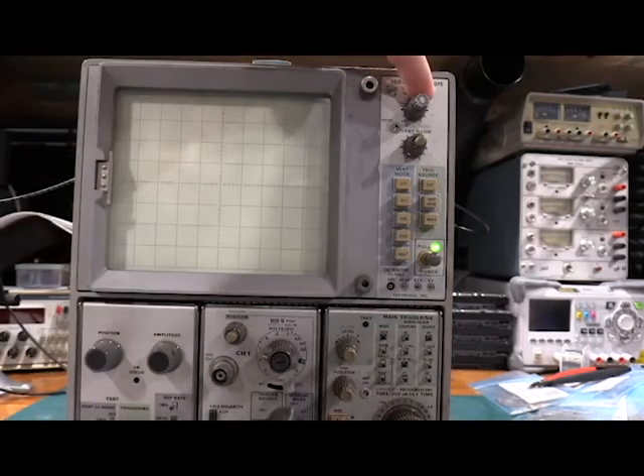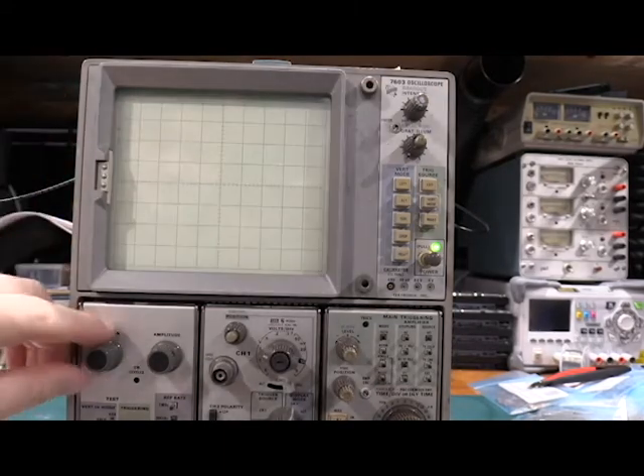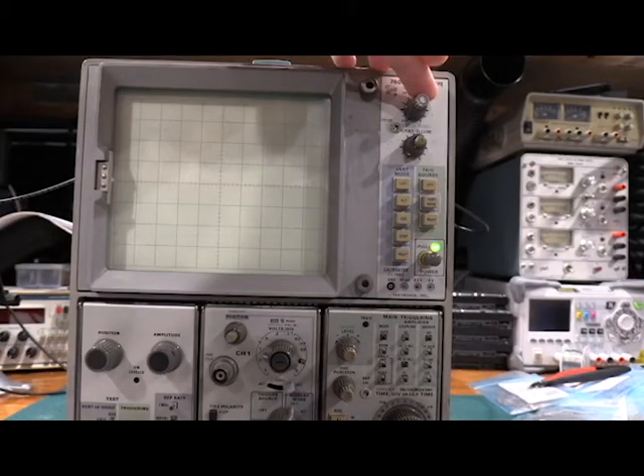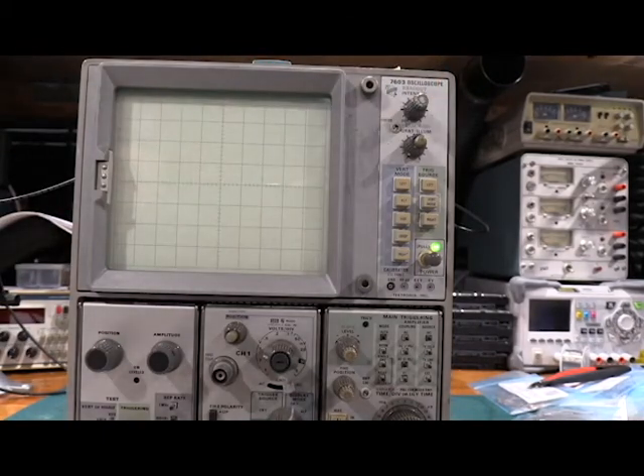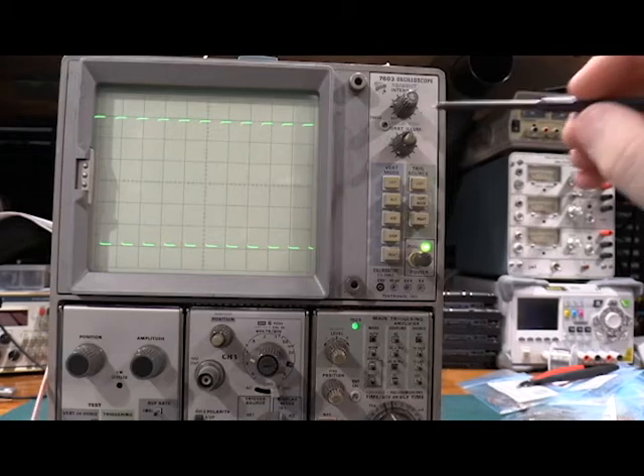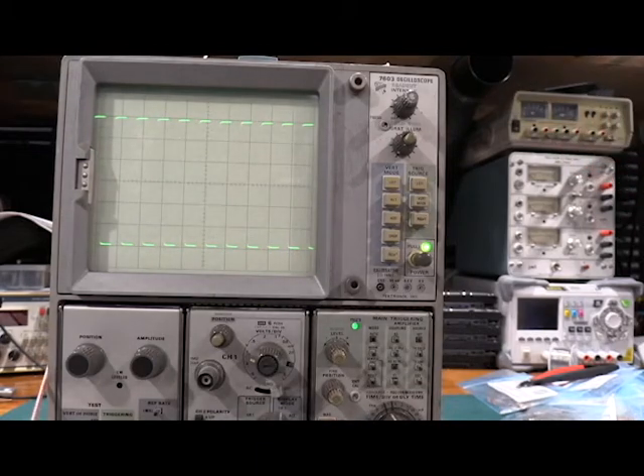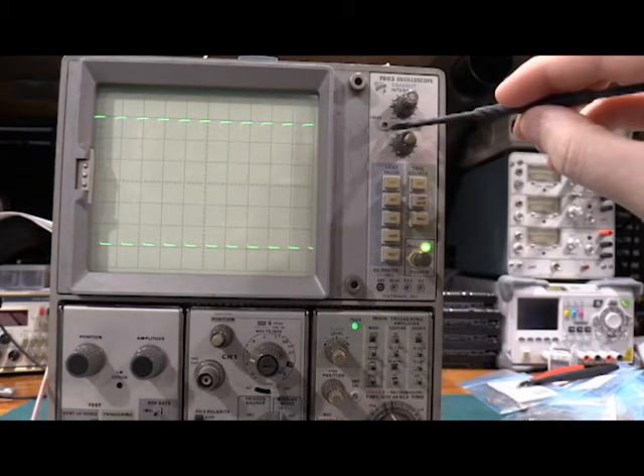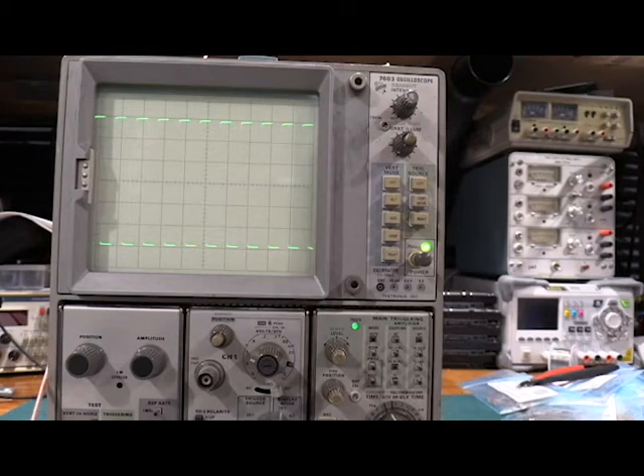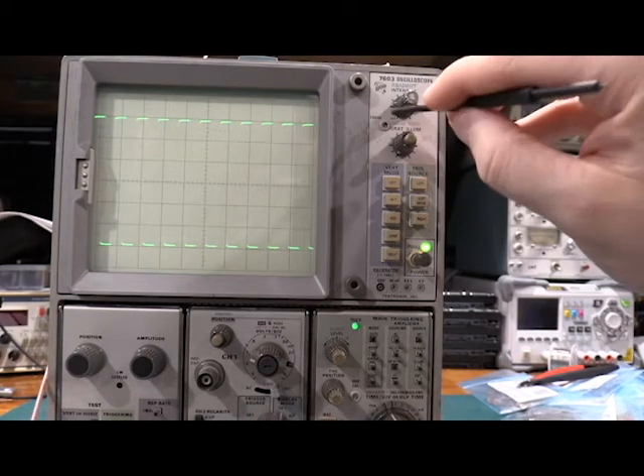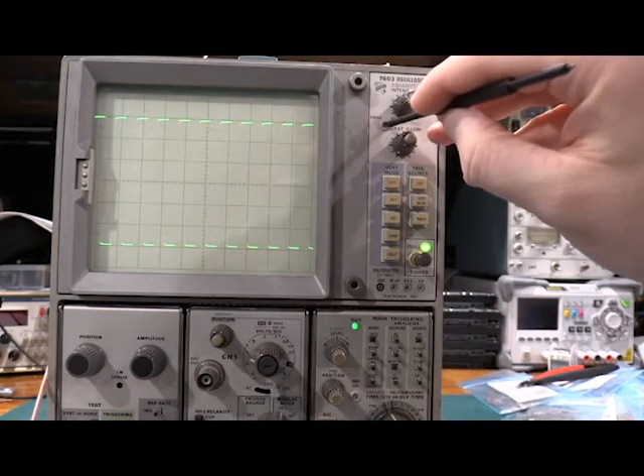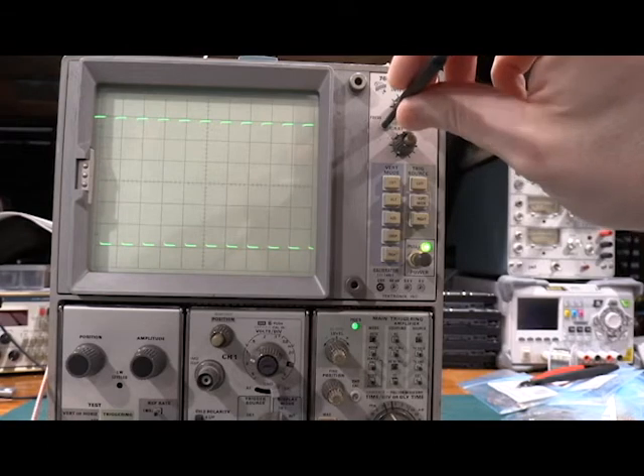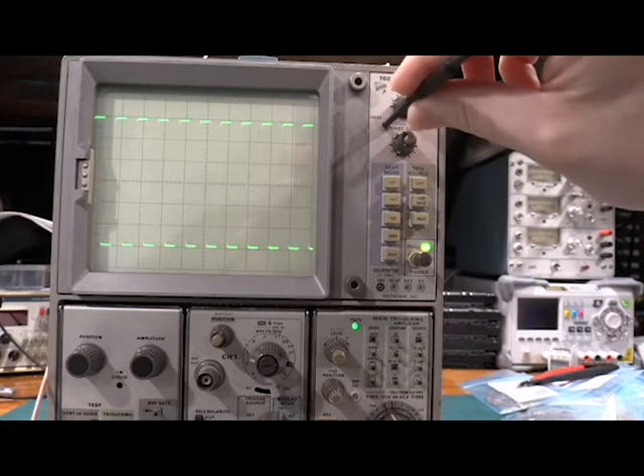Also, since I've done the DC bias, I got some intensity back on the screen, so this tube is actually nice and healthy. Okay, I have all the signal sources set up. We need to adjust the focus control, and then we need to adjust the astigmatism control, which is back on the Z-axis board in the back of the unit. But the adjustment we're looking for is a well-defined display, so that's getting more fuzzy.